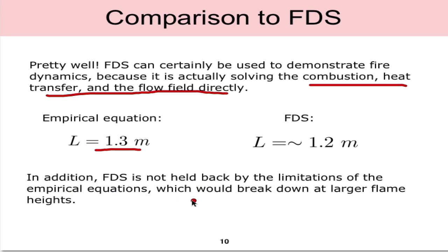Whereas our empirical equation is using previous data sets to estimate what the flame height would be. Additionally, FDS is not held back or limited like the empirical equation. The empirical equation would break down at larger flame heights, any flame height that would be outside of that experimental data set the relationship would begin to break down. Whereas in FDS we could always make a larger heat release rate or larger burning area and because it's solving for the combustion and physics directly we'd be able to use it for a wider range of problems.